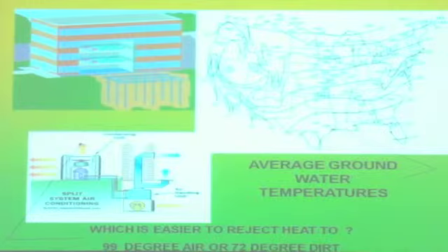That's roughly kind of a metric. If you want to go 300 foot deep, then the amount of square footage that you have to air condition is how much square footage of soil you need to build that heat exchanger in. Could you repeat that metric one more time? Square foot of conditioned space. So if you stack it vertically, you need that much square footage of soil on the surface. Assuming 300 feet. Yeah, assuming that you're only going to go 300 foot deep.